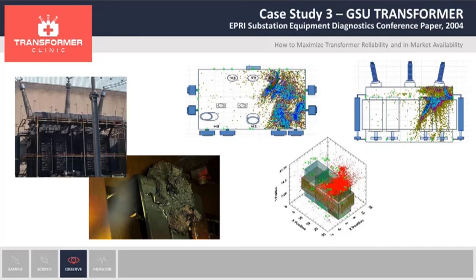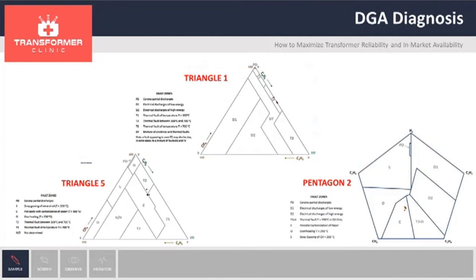So they found it on time. When we look at the DGA, we found an excellent correlation. As you can see on the photograph, there is no paper insulation involved. When looking at the DGA diagnosis, Triangle 1 is telling us we have a high temperature thermal fault on the transformer. Triangle 5 is between carbonization and high temperature fault on the oil. And Pentagon 2 is telling us we have carbonization, which is what we saw on the internal inspection.